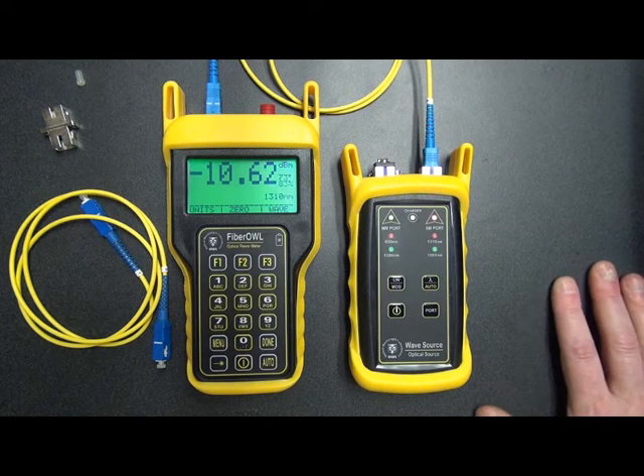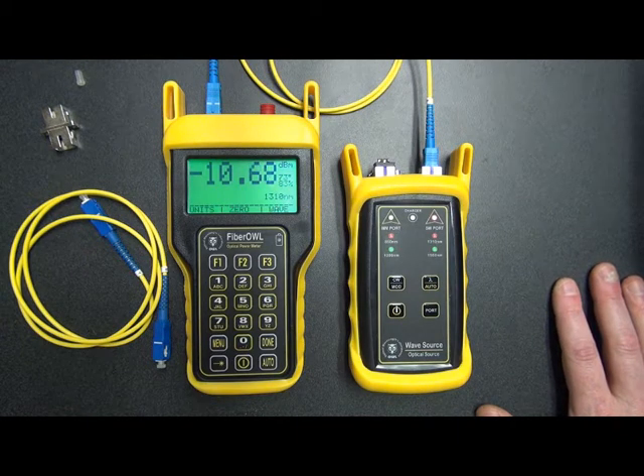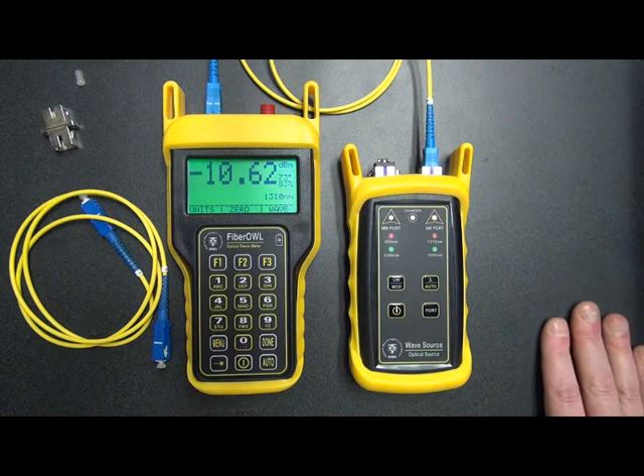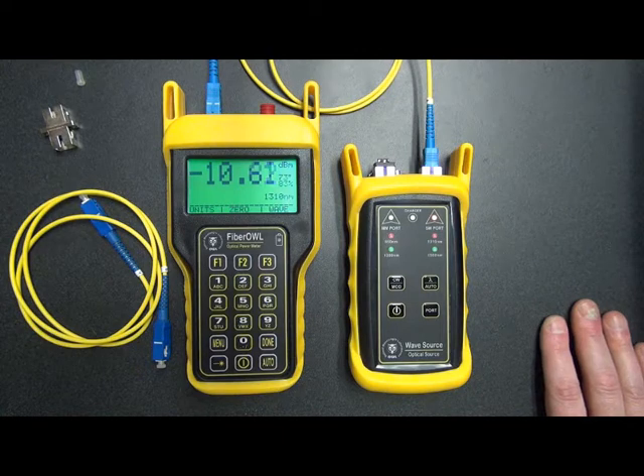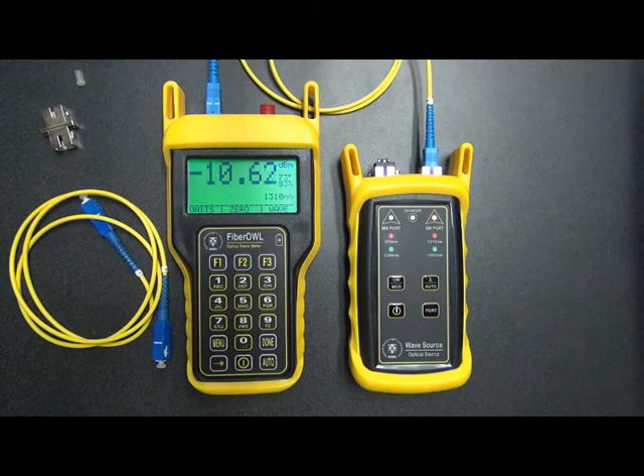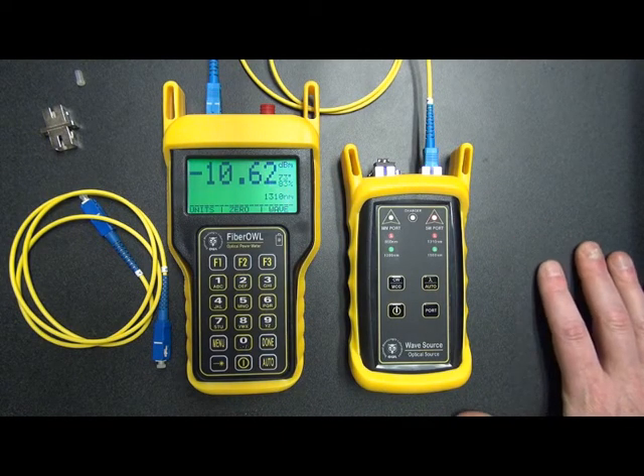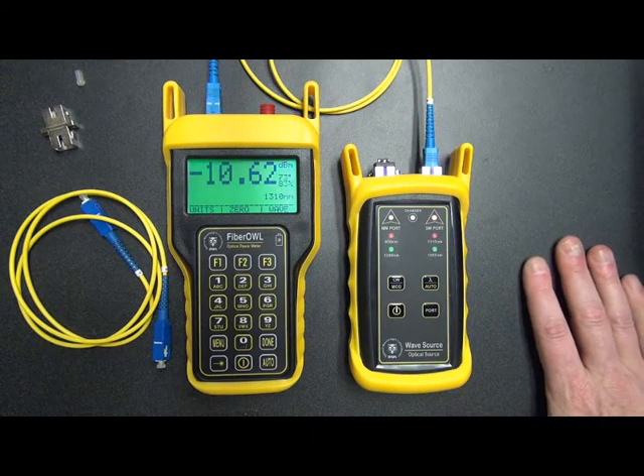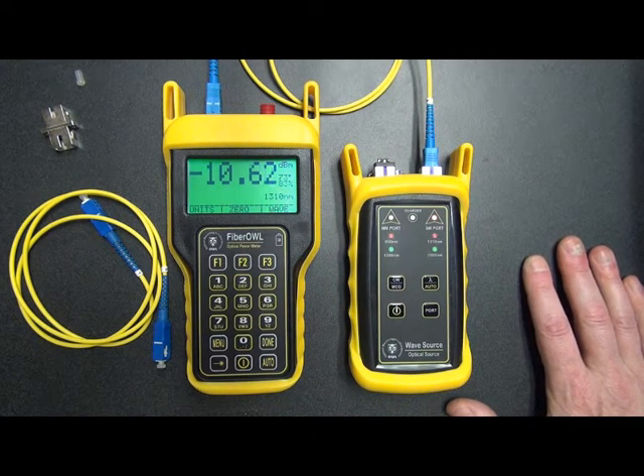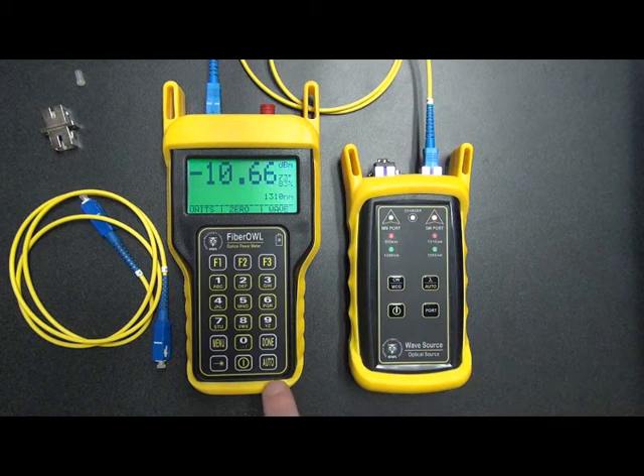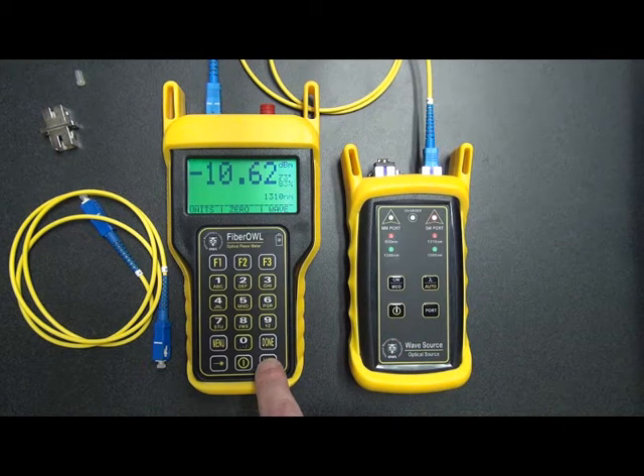So we would have to switch both units to 1550 nanometers to check that wavelength. But what I'd like to do here is demonstrate a nice feature of the FiberOWL and the WaveSource when used together, and that's called auto mode. Auto mode allows the wavelengths to switch automatically. This is simply done on the FiberOWL by pressing the auto button. You'll see it says auto on.